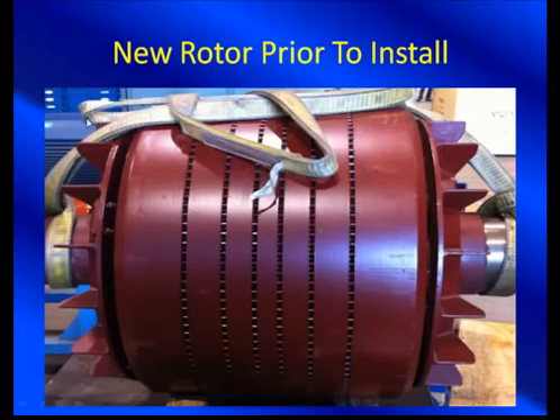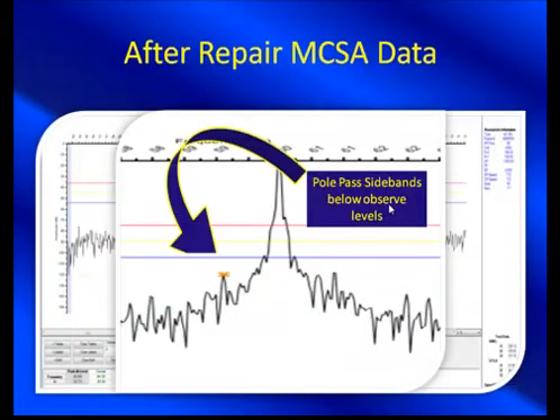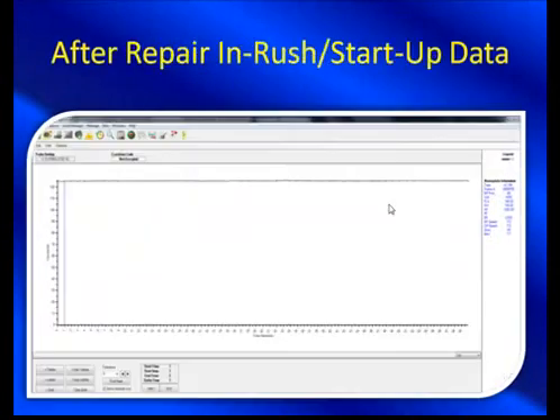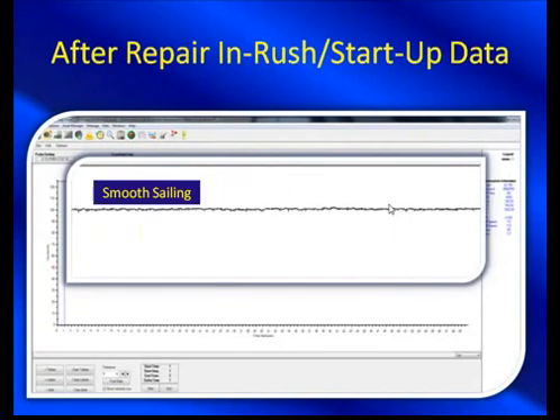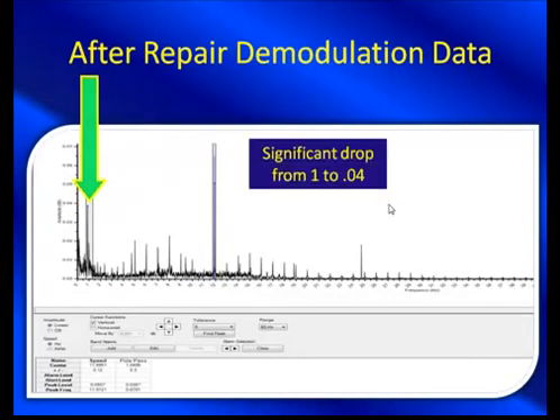Here's our new rotor — we don't have those white lines on it. They definitely don't come pre-designed with lines; only after you exhibit problems do you have that. This is going into the system, and of course we want to take some follow-up data once it's back in operation. That's awesome — such a large reduction in that pole-pass sideband. When we look at our inrush startup data again, we see smooth sailing: no choppy water, no 10-amp swings. So we knew this wasn't load-related. All important changes went away with the fixing of the rotor bars. After repair demodulation data: we went from 1 to 0.04 — over a thousand percent drop in pole-pass amplitude, which is a great sign for a good rework. Set this as your baseline and move forward with quarterly or annual testing.